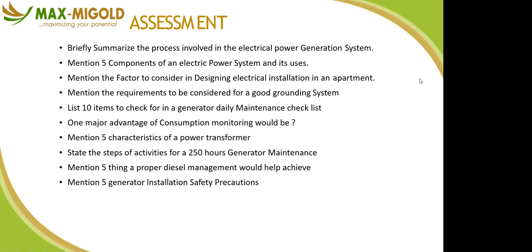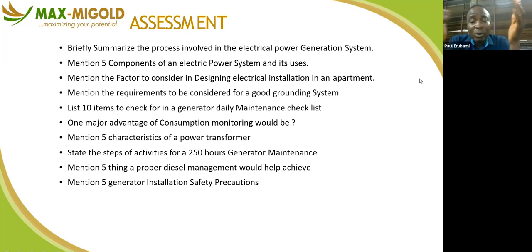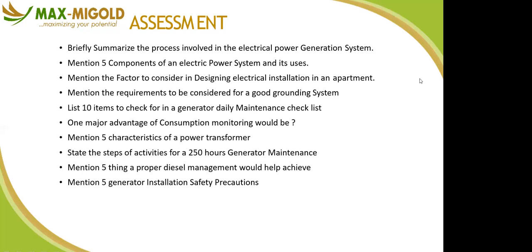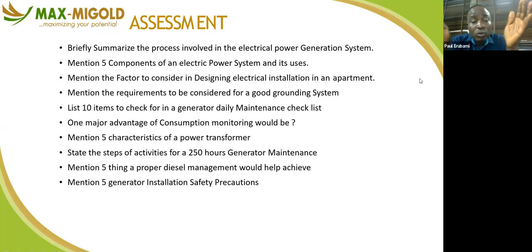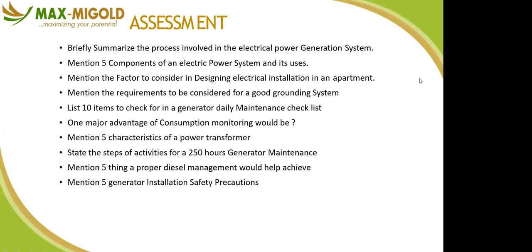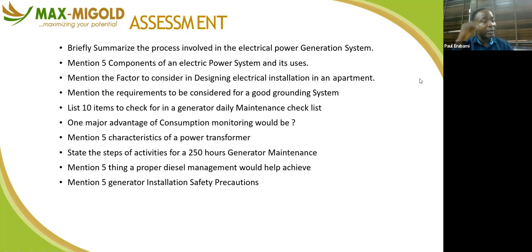So when you want to make some changes, you leave the existing and go with the current one. You make provision for the two. In case I have full capacity, I should have something in place to power that. Now that I have this, I should maintain this, and in the long run you are saving costs. But that higher one should be left there in case you want to run the entire building. If there is a possibility of running the entire building, you don't need to start hiring a generator, you have it in place already. What you need to do is buy a smaller generator that can meet your current load demand. Is that taken?